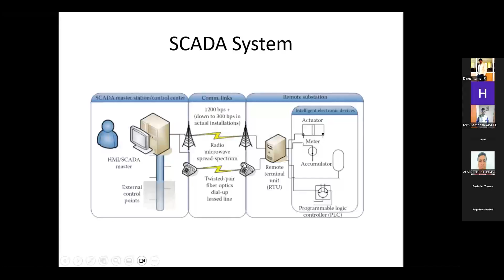These IED devices detect the situation, like the frequency, the voltage, the current - every data is determined using this remote terminal unit that sends the information. It is transmitted to the master control center or national control center through different types of communications - fiber optic, radio, microwave - any communication medium can be used in SCADA systems.